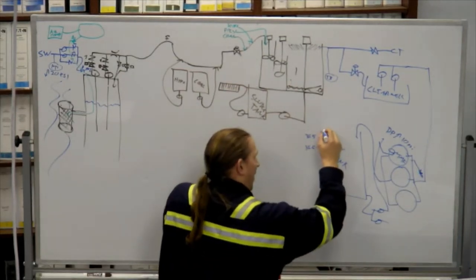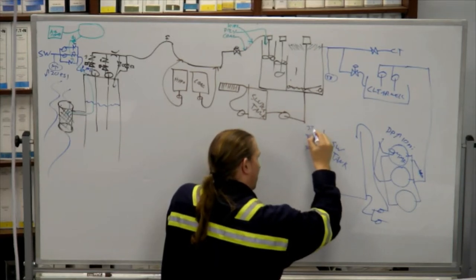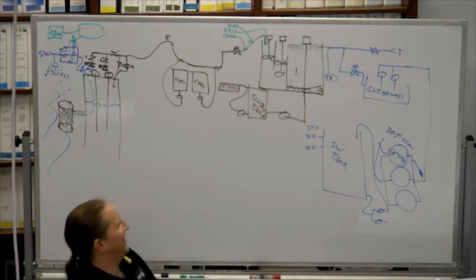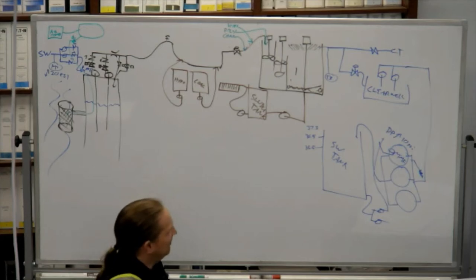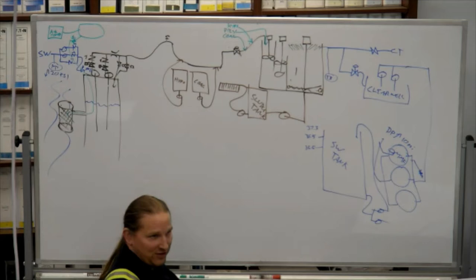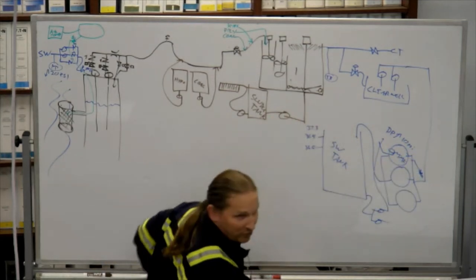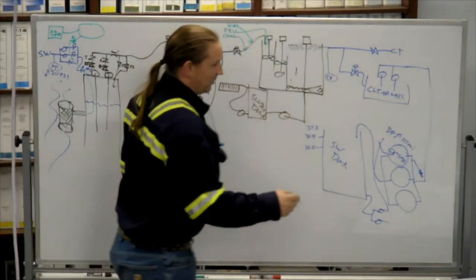And then, how full is full? 37.8. 37.3. It will never ever show 37.4. It will get up to 37.3 and then start putting however much you're putting through these multimedia filters on the ground. How much is that? 600 gallons a minute each?